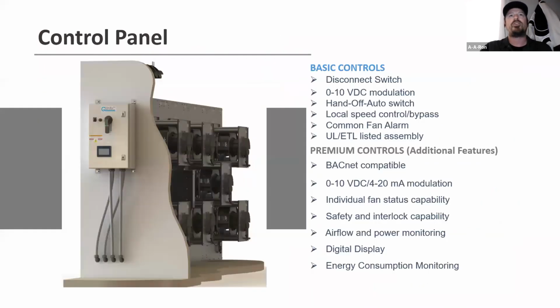So we talk about basic and premium controls. I always recommend premium controls. While there is an upcharge for it, the benefits that you get from it far outweigh the basic controls. But if it's a simple 1 or 2 fan system and you just have a 0 to 10 coming in, a basic control gives you everything that you need. Both systems come with an HOA switch and a potentiometer for bypass control. So if you ever lost building control, you can just switch it into hand mode and use the dial to dial in the fan speed that you would need.